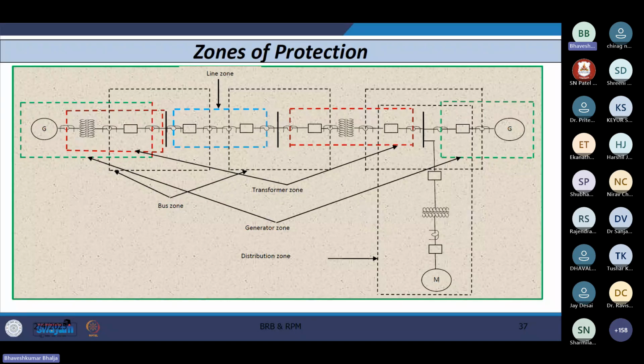If faults occur in apparatus like a generator, transformer, induction motor, or bus bar, then the location is not important because it is very minimal. It is hardly within the substation, because all these power transformers and generators are within the substation or switchyard. So in that case fault location is not required. Classification is required so that a person can take the necessary measures. If a fault occurs in a transformer, then you have to isolate the circuit breakers at both sides of the transformer and then do the maintenance. So this is already there.